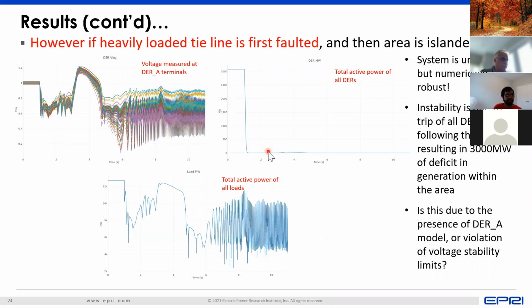So we have to really pay close attention to parameterization here, because let's say this DERA model was not parameterized to showcase the tripping that occurs. If you see here, the voltage stayed below 0.89 per unit for greater than 2 seconds when the DER finally tripped. So let's say you didn't parameterize the model to take this into consideration, or you didn't even represent the DERA with this kind of a voltage trip, then when you're doing a transmission study you would have assumed that everything is going to be fine and we will continue to remain stable, which means we don't have to plan for this kind of an event occurring. But having this model parameterized in a good way really brings to light all of these instabilities that may occur.